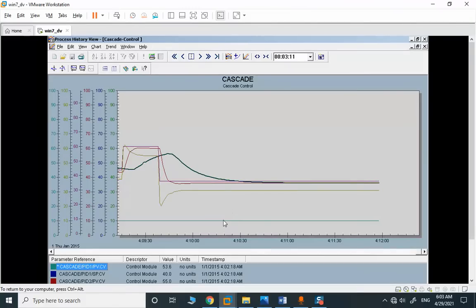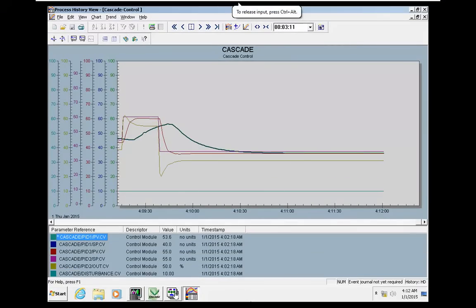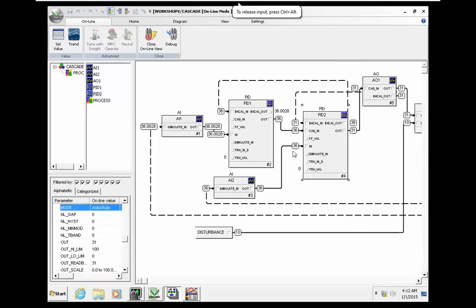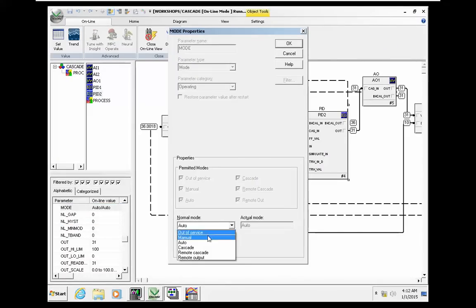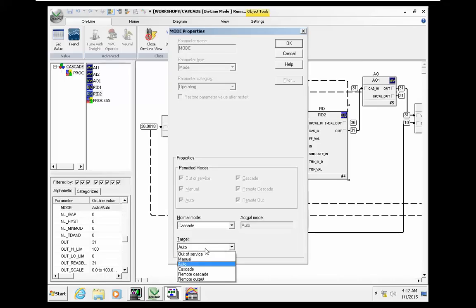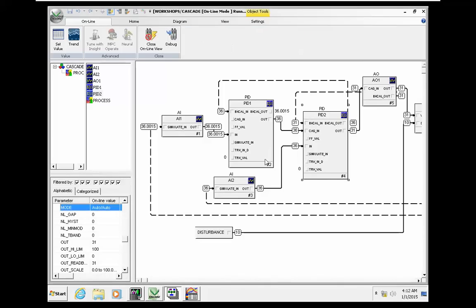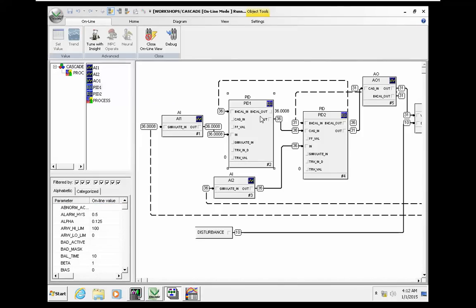So PID1 should be manual, PID2 in cascade. PID2 is in automatic. I change PID2 to cascade, and when PID2 is in cascade, the setpoint of PID2 is provided by the output of PID1.